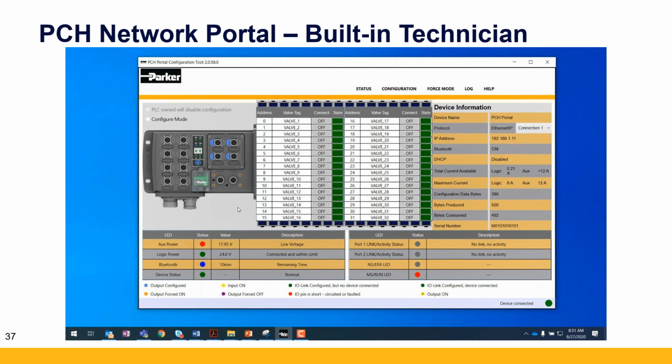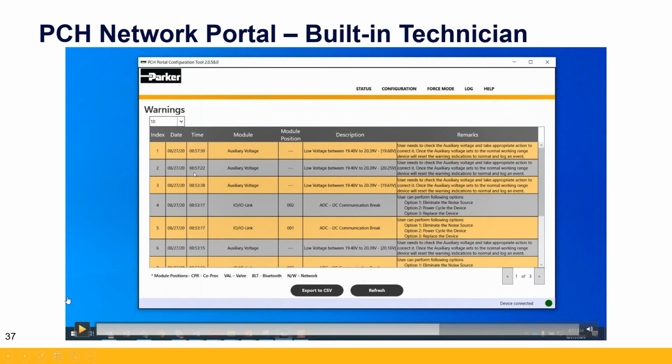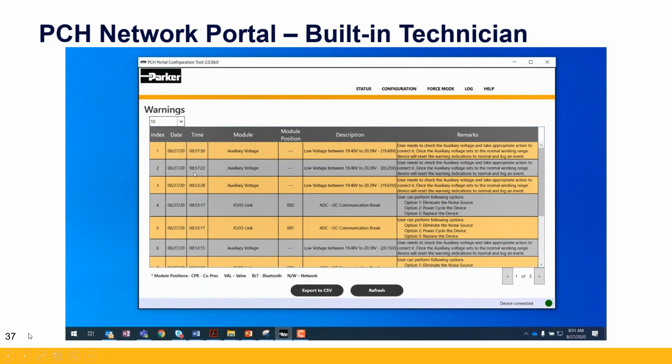Now, for parameter diagnostics and process diagnostics, we have different things in them. I told you what's in that process data. In the parameter data, you get things like aux logic, voltage reading, cycle counting, all that good stuff. We're also making a lot of function blocks and AOIs for folks for integrating these things. There's a lot of diagnostics built into this, 237 total diagnostics that we can communicate. But let me show you what that looks like.